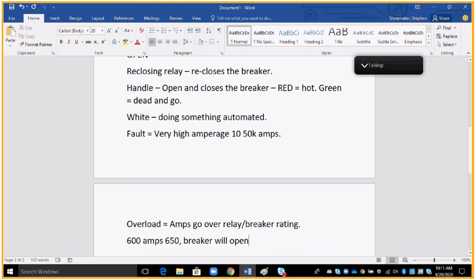All right. And this is dependent on the company and what they do in situations. They'll have a certain percentage set for the relay. You can adjust the relay. And if they want to get real tight and say, well, it's rated for 600, I want it to send an open signal at 610, then they'll do that. Or I've got it rated at 600 and I actually feel comfortable with going to 700. That's all in their design as far as their circuit and breaker relay is concerned. That's completely up to them.